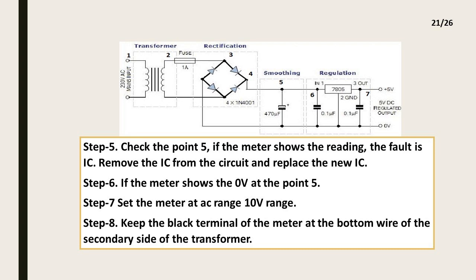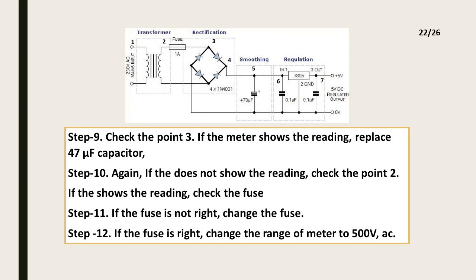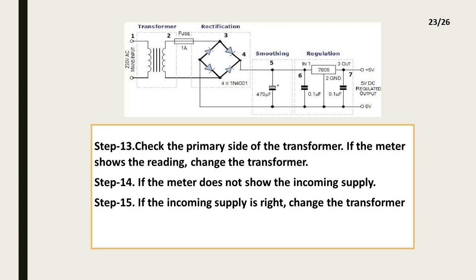Step 10: If the meter does not show a reading, check point 2. If it shows a reading, check the fuse. Step 11: If the fuse is not right, change the fuse. Step 12: If the fuse is right, change the meter range to 500 volt AC. Step 13: Check the primary side of the transformer — if the meter shows a reading, change the transformer. Step 14: If the meter does not show the incoming supply, Step 15: If the incoming supply is right, change the transformer.